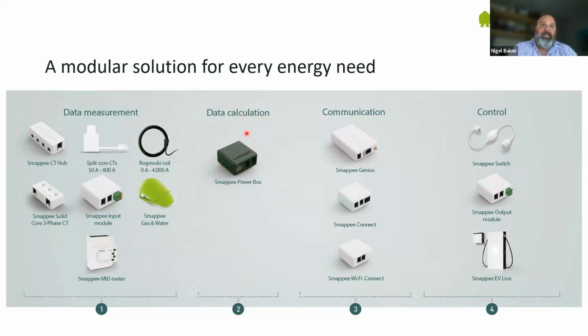Our main data collector from the voltages is the Smappee Powerbox. That's where your voltages go in, and that powers up the entire system. There's only one voltage connection, and you can do single phase, three phase, even dual phase. You can do three phase star or three phase delta connection, and as I mentioned, it's a 50 or 60 hertz system.